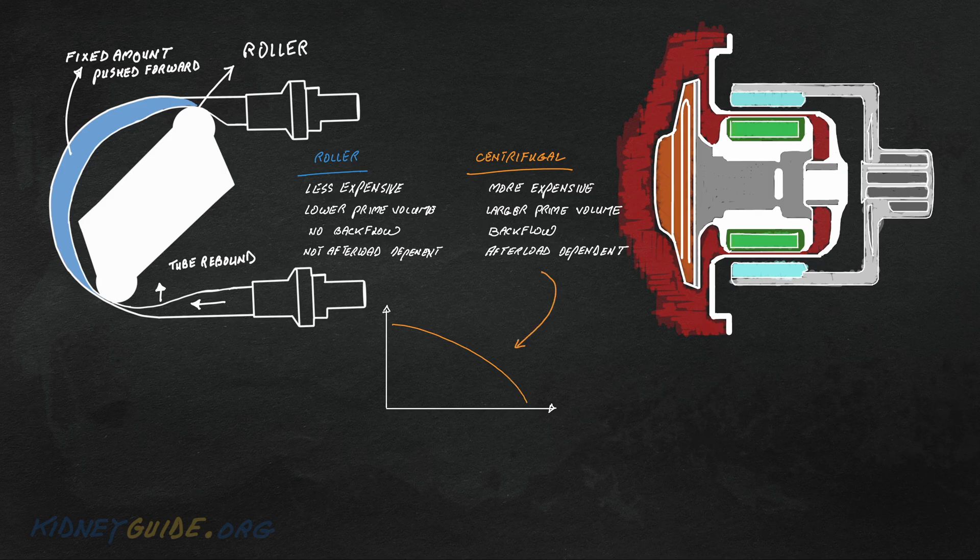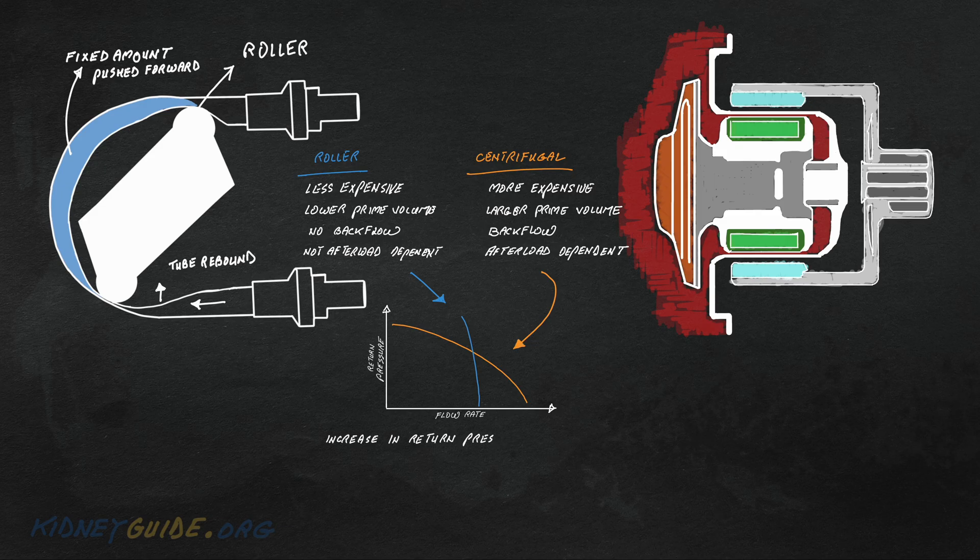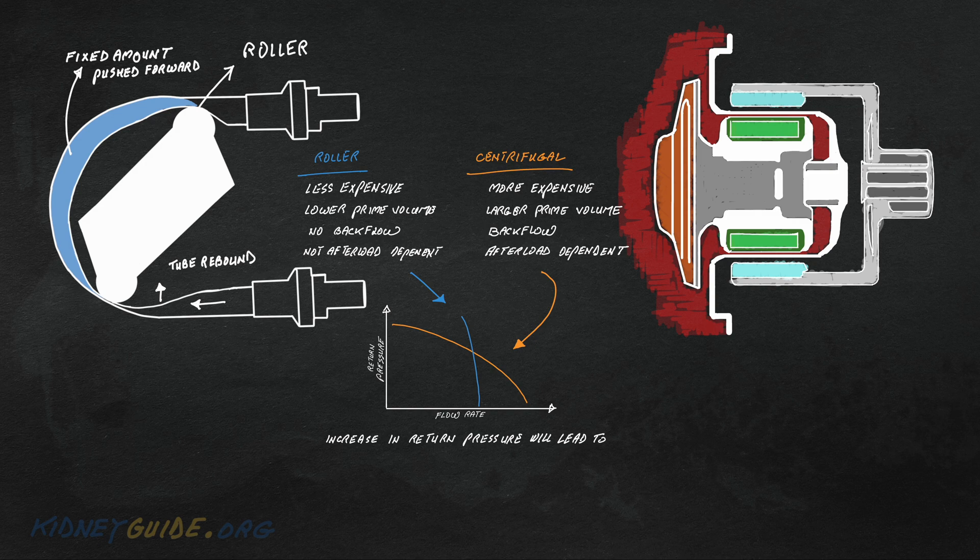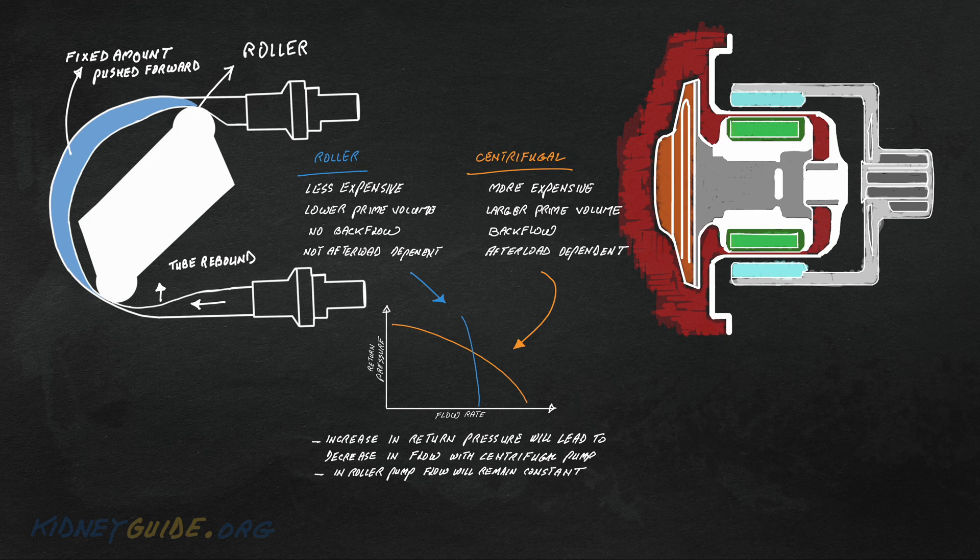Whereas centrifugal pumps are afterload dependent, which is safer in situations where there is a sudden rise in pressure, which then leads to decrease in flow and avoid catastrophic events such as dissection or cannula disconnection.